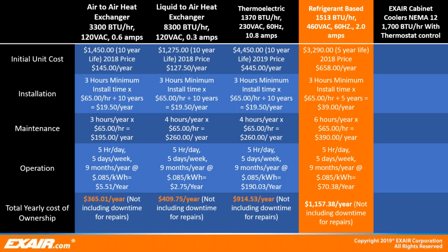The upfront purchase price of this refrigerant-based unit is $3,290. Spreading that cost over the manufacturer's expected service lifetime of 5 years, we come up with a $658 per year cost. Using 3 hours as the minimum to install, at a service rate of $65 an hour, spreading that over the 5-year service lifetime, we come up with $39 a year. Using 6 hours as the minimum for yearly maintenance and a service rate of $65 an hour, we have a yearly cost of $390. The final expense going into the total operation cost is the electricity draw.